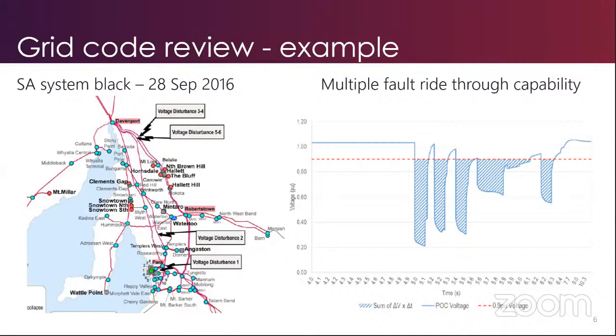But what happened during that time is that SA was rich with a lot of wind farms at the time. This wind farm had a voltage dip counter, which was set to trip the wind turbines after a certain number of dips. So each voltage disturbance increased that counter, and after some time, these wind farms started tripping. A number of wind farms tripped. As a result, the generation requirement increased, and the power started flowing through the interconnector, and it exceeded the interconnector limit and tripped. So in summary, that was the event.